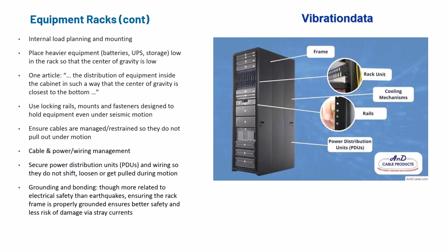Some advice on internal load planning and mounting—this is all common sense. Place heavier equipment, batteries, and uninterrupted power supply storage low in the rack so the center of gravity is low. Design the distribution of equipment inside the cabinet so that the center of gravity is as close to the bottom as possible. Use locking rails, mounts, and fasteners designed to hold equipment even under severe seismic motion.